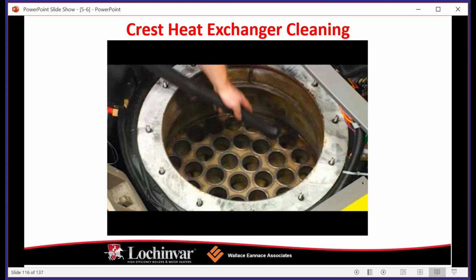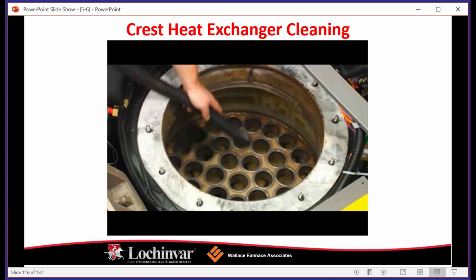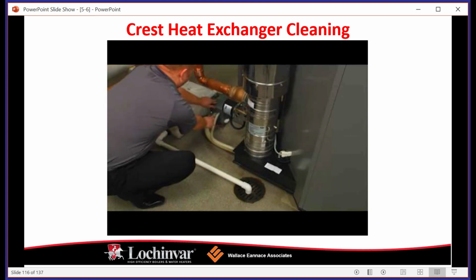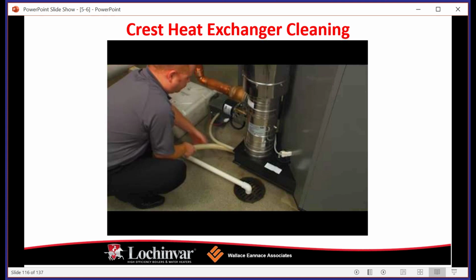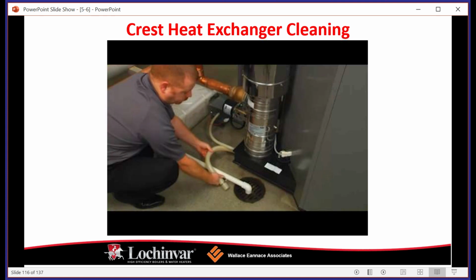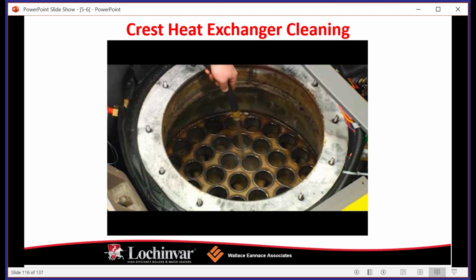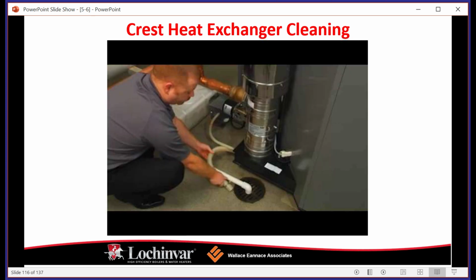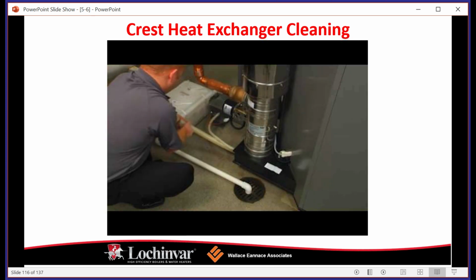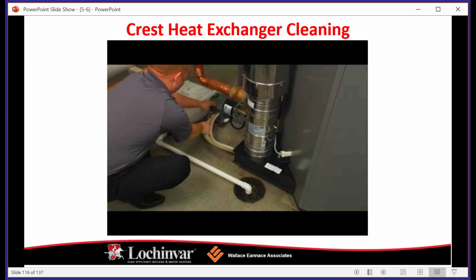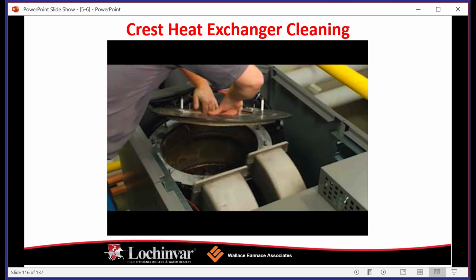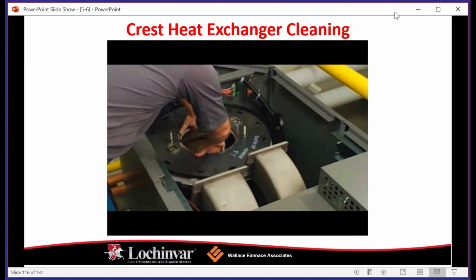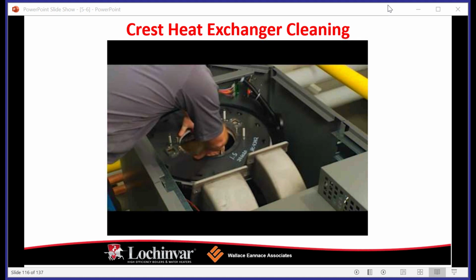Grasp the upper front panel at the bottom sides. Pull the panel away and up from the boiler. Grasp the lower front panel at the top sides. Pull the panel away and up from the boiler. Locate the on-off switch on the lower left side of the control panel. Turn the switch to the off position. Turn off the main gas supply to the boiler at the main manual gas valve.